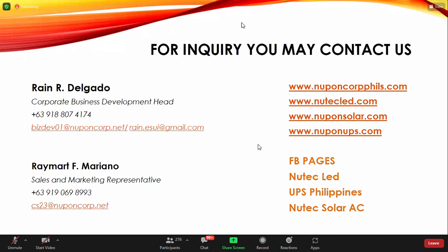Jaime Ventanilla. Yes, sir. I just want to clarify. Maybe I overheard or did not hear that. The AC unit is a DC unit, DC voltage? It is full DC, yes. So it is solar directly, completely can run during the day. No battery, no grid. So meaning if it is DC, there is no frequency at all. Yes, it doesn't need it. And because it's high voltage, it doesn't matter how long the wire is from the solar panels.